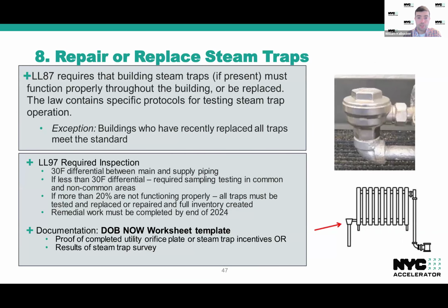So there is a big parallel here with Local Law 87. 87 does have a steam trap testing requirement. Buildings can sort of skirt that requirement or be exempt from it if they have recently replaced all of their traps already. But with regards to Local Law 97 inspection requirements, for two-pipe steam systems, there's generally going to be a temperature differential between your main supply and return. That temperature differential is indicative of a healthy system. If you have a low differential between your steam supply and your condensate return temperatures, that might indicate that you have systemic broken steam traps, which are going to require attention and replacement. So if it's found that there is a low temperature differential in your supply and return, then you're going to have to start testing steam traps at a sampling rate. And if more than 20% of those steam traps have failed, then all traps in the building need to be tested and then either repaired or replaced if they're found to be broken.